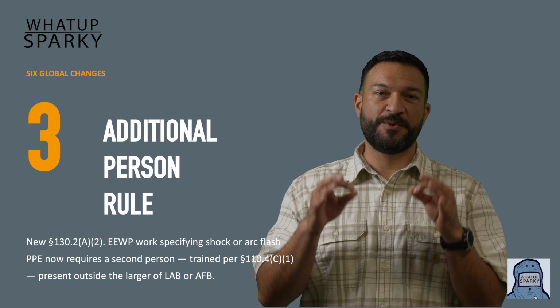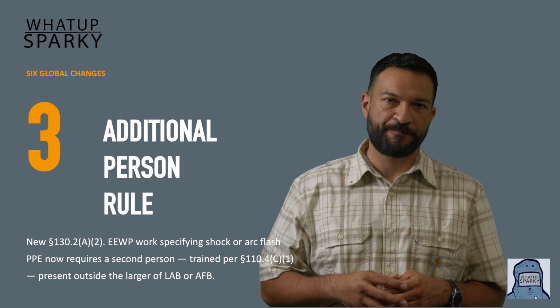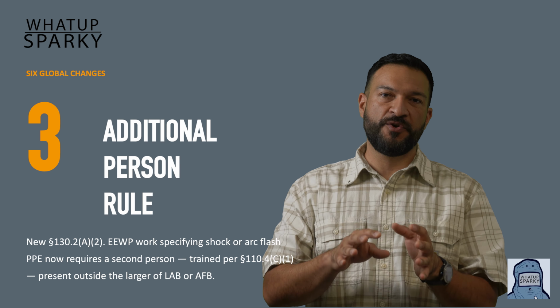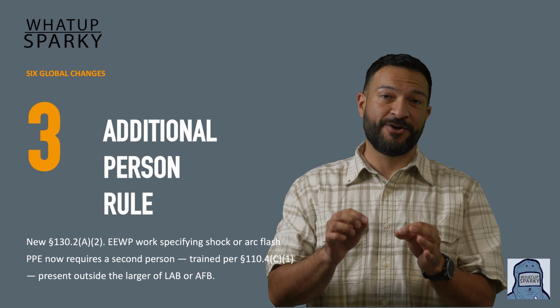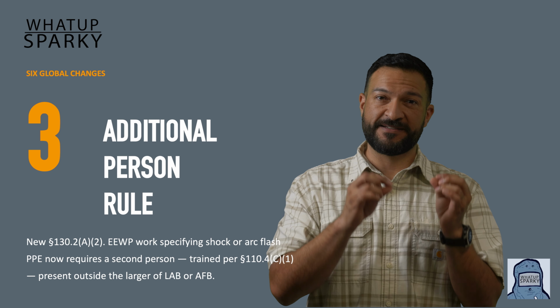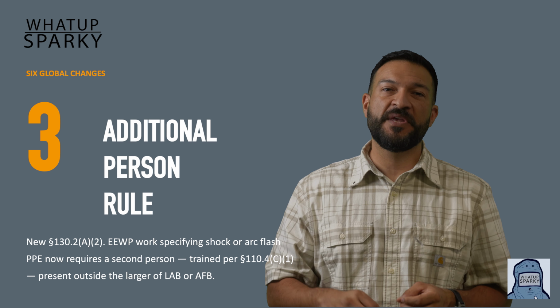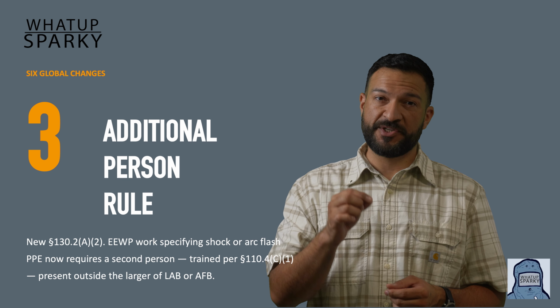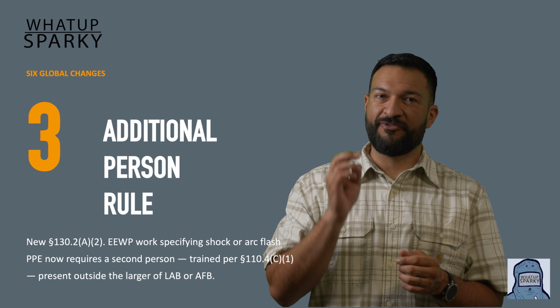Three, the additional person rule. This is a big one. The new 130.2A2: when an energized electrical work permit specifies electric shock or arc flash PPE, you now need a second person, and they need to be trained per 110.4C1, which is emergency response. That also includes contact release, which are ways of dealing with someone who's being shocked, not just CPR or first aid. They need to be present at the work, and they need to be outside the bigger of the limited approach boundary or the arc flash boundary. We need them to stay safe to do the rescuing.